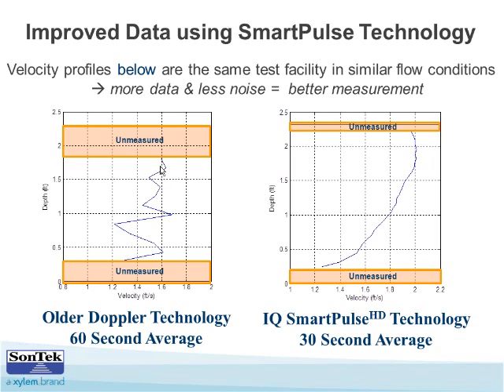And if you can draw a curve through that, if you averaged it long enough, you'd get a decent curve and be able to glean enough information. But what we have now with the new technology, the new transducer technology, the new proprietary flow algorithms, just to name a few, is with less averaging, you really don't even have to draw a curve. The data itself is a curve. And not only that, but you have less guesswork to do with unmeasured surfaces. So there's less extrapolation to do at the bottom, because instead of a blanking distance of a certain distance for other instruments, we actually have data down here. So there's just less guesswork down here, and then there's less cutoff at the top.